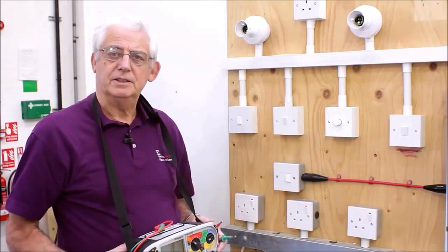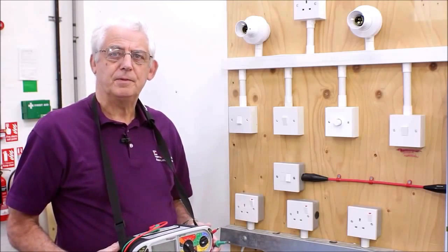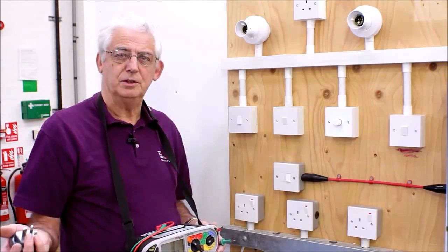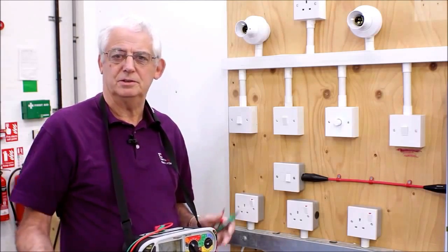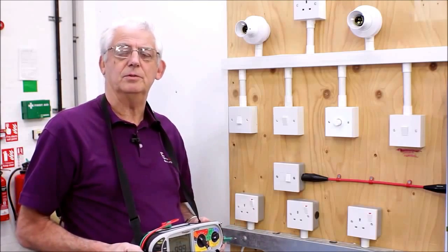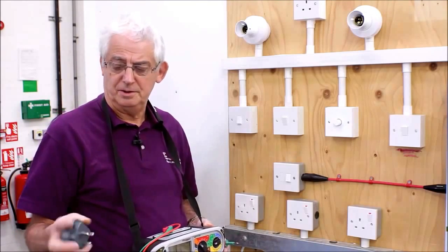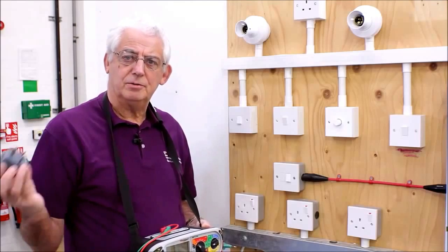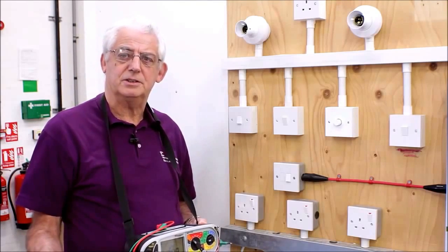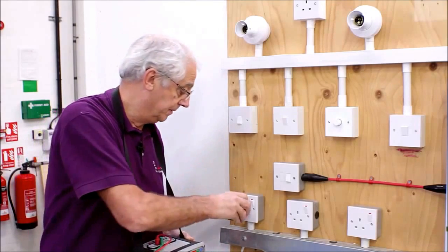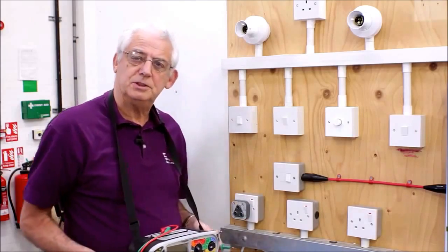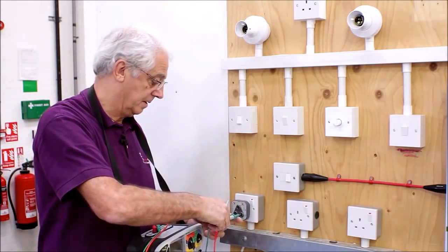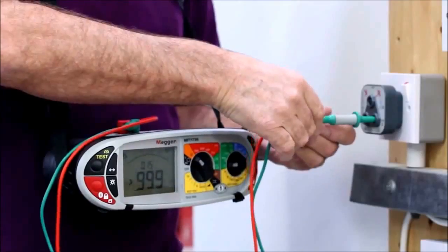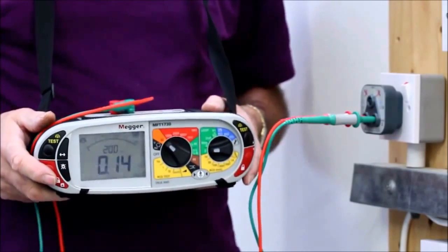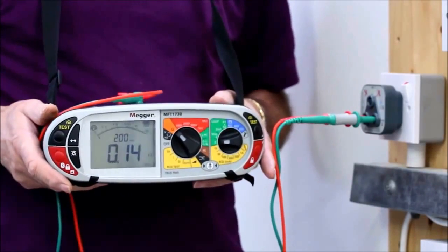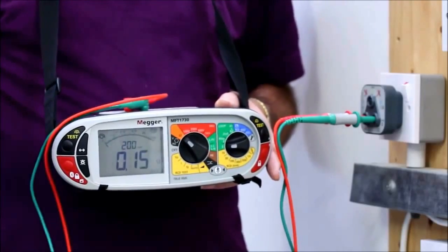I've now cross-connected the line and neutral conductors. It doesn't really matter whether you do the line and neutral first or the line and earth first. There's no preference, but of course the value you record is the one between the line and earth. I need to go again round every socket and test now between line and neutral. Need to make sure the switch is turned on. Put my probes in, and I should get a value again of around 0.15.